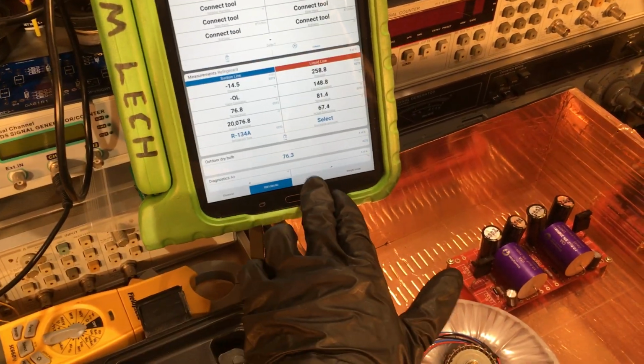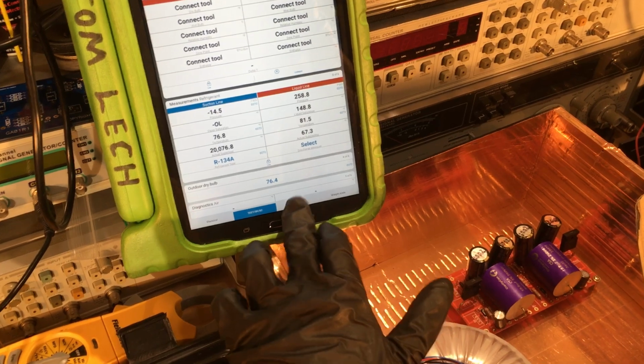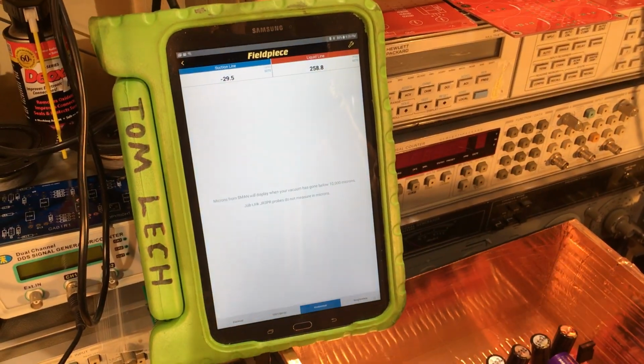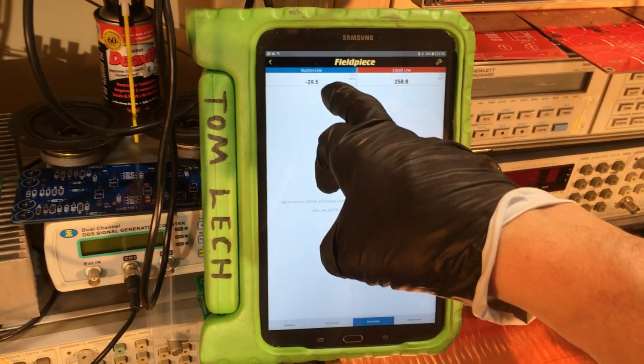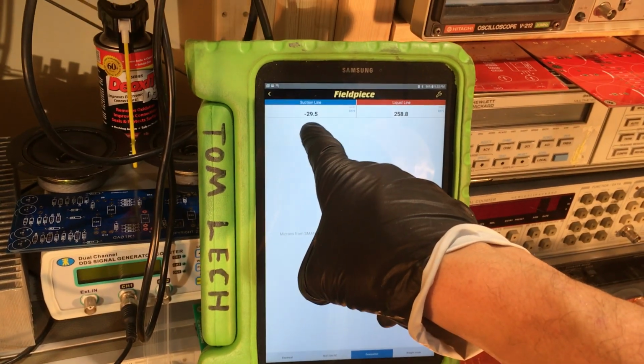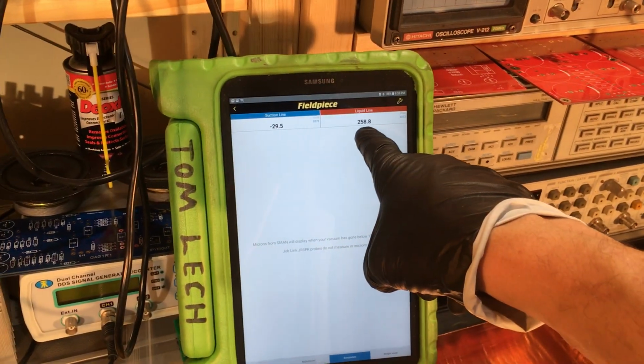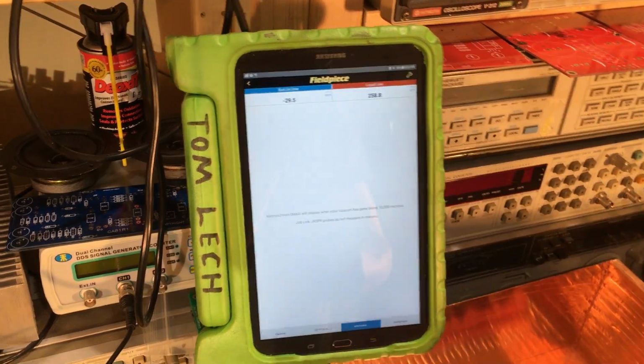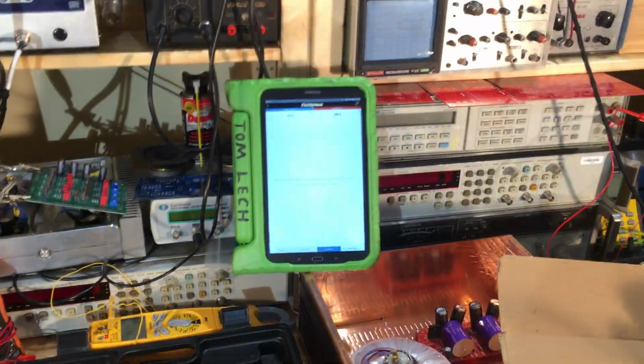Let's go over the vacuum evacuation. Okay, so this is the evacuation mode. And we can see my suction line is still at 29. I never opened up. I'm at almost 260 over there. Actually, it dropped a little. So there is a small leak in these gauges. Very small, but there is.